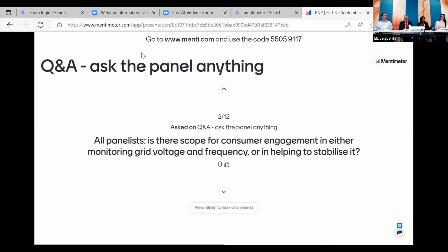But most of the converters, almost all the converters installed on our grid at the moment, are something called grid following. They don't have a voltage reference. These are current source converters, and they follow the grid. So if the voltage changes, the converter changes its voltage; if the frequency changes, it follows the frequency. Being a grid follower rather than a grid former, it's not really helping in the case of faults, or helping to dampen oscillations, because it doesn't know anything but to follow the grid.